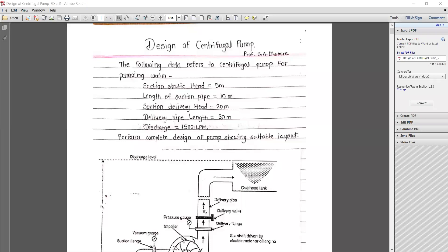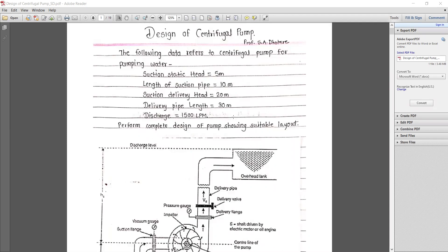Hello everyone and welcome to this DMS lecture. In the previous lecture we discussed the theory regarding pumps, specifically the centrifugal pump. Now let's see how we can design a centrifugal pump. We start with a simple numerical design problem. The given data includes: suction static head of 5 meters, suction pipe length of 10 meters, static delivery head of 20 meters, delivery pipe length of 30 meters, and required discharge of 1500 liters per minute.